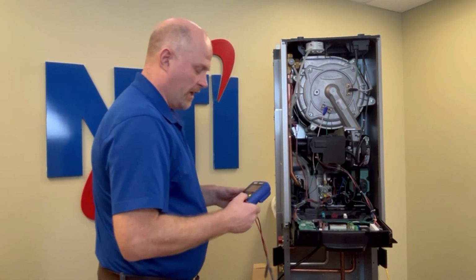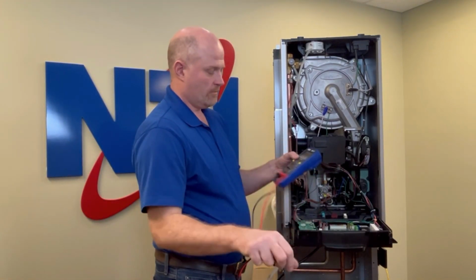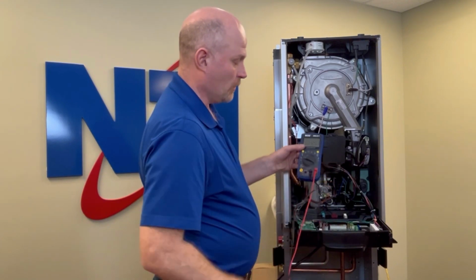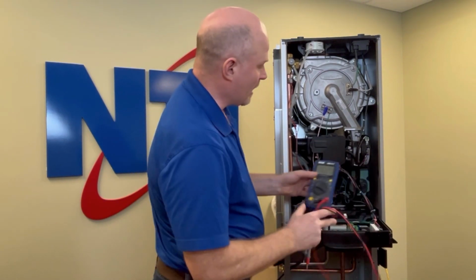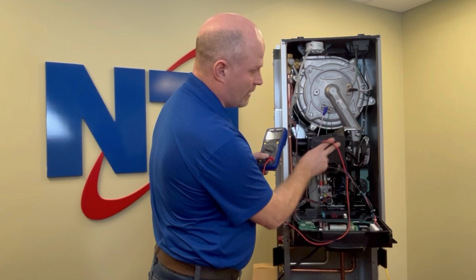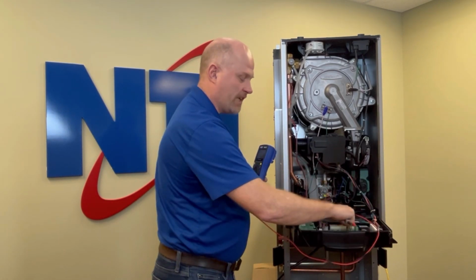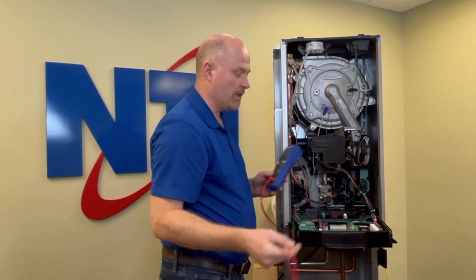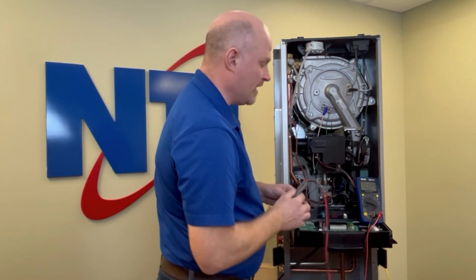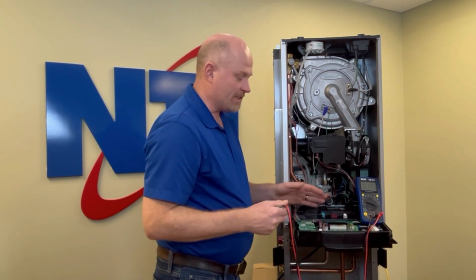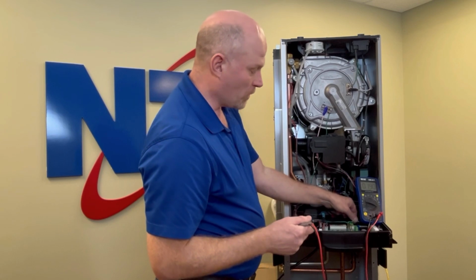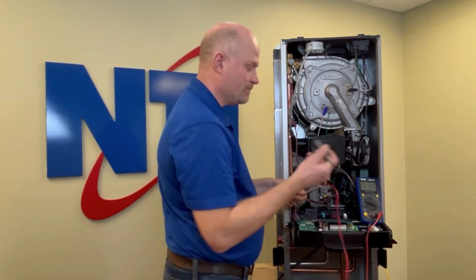To do that, you'll want to get your voltmeter. We're going to set it to volts AC. And the power comes into this boiler up here in the junction box and then follows down to the main circuit board on this green plug. You could test at either location, but I recommend testing right next to the boiler in case there's a poor connection inside the boiler for some reason.